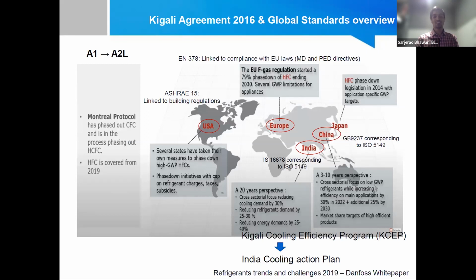If you see the USA market, it is more driven by the ASHRAE 15 standard, which is linked to building regulations. As of now, the USA has not accepted A3 refrigerant. They have accepted only A2L as of today's date. They have a strict charge limitation of up to 150 grams, and they have not moved beyond that. So that's the USA scenario, that is the North America market scenario.